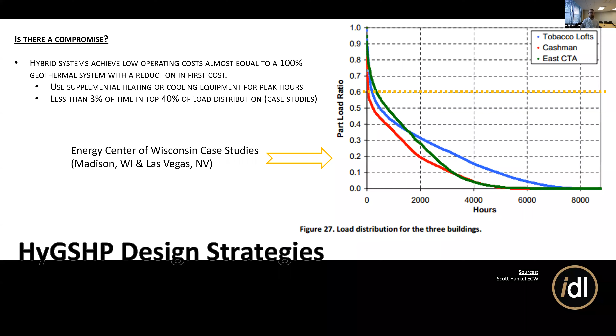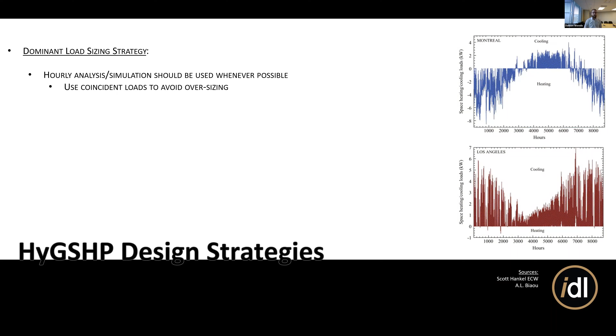Really rely on hourly analysis, not just rule of thumb, and make sure that you're not oversizing the system, thinking that everything terrible is going to happen on the same day, like everybody's going to be in the conference room at the same time, that all the lights are on the hottest day of the year. Look at how the office is actually being used to avoid adding that extra safety factor.